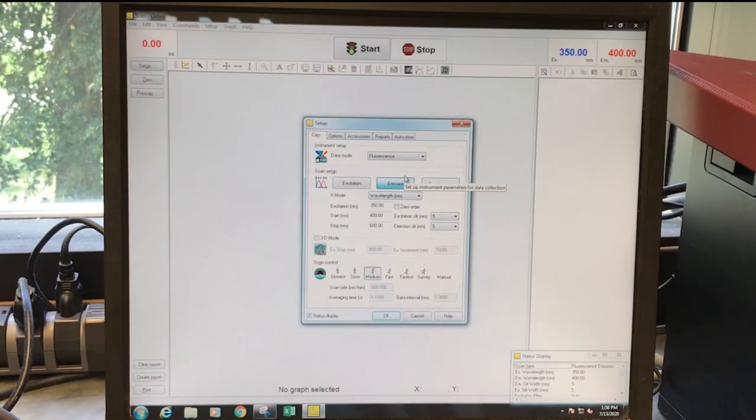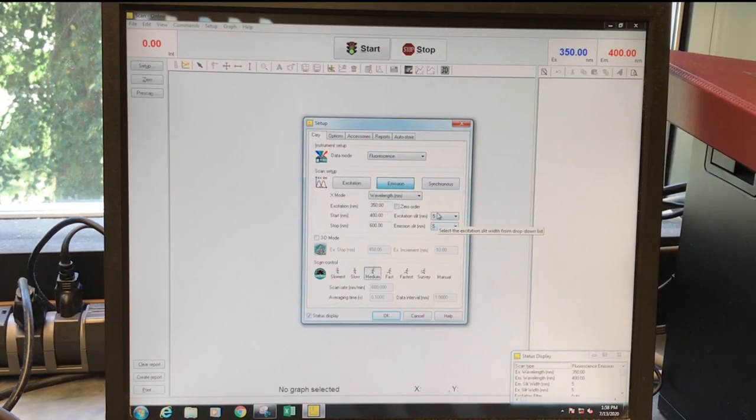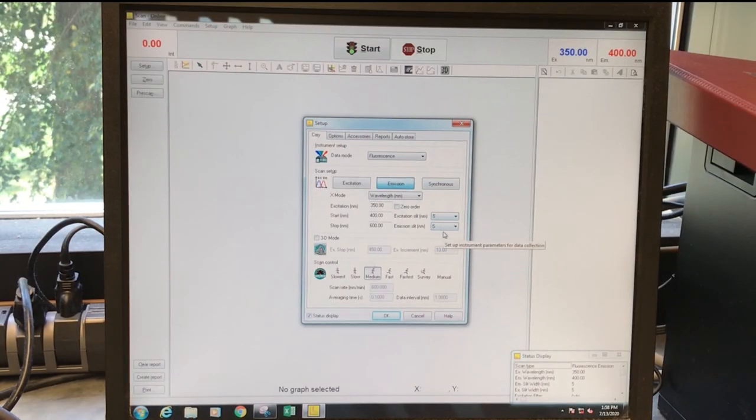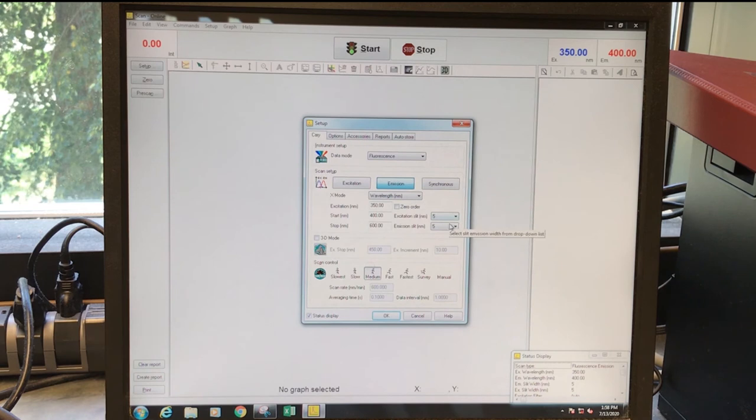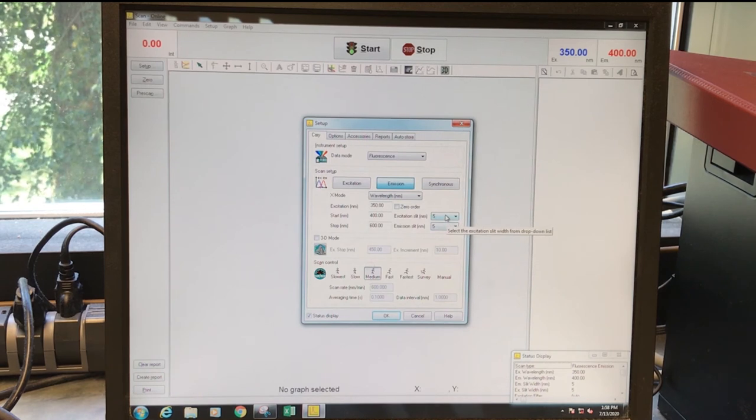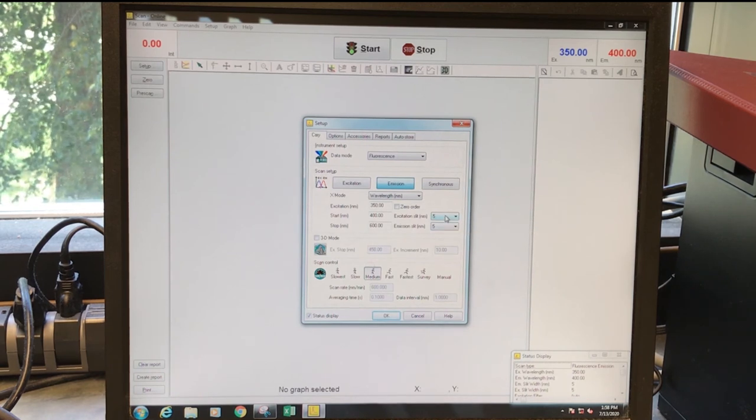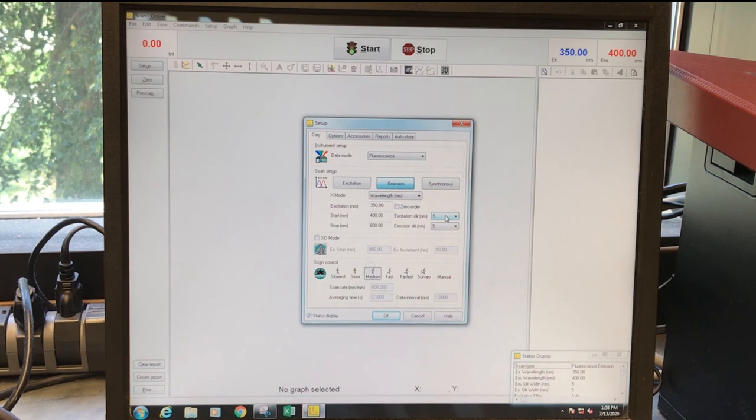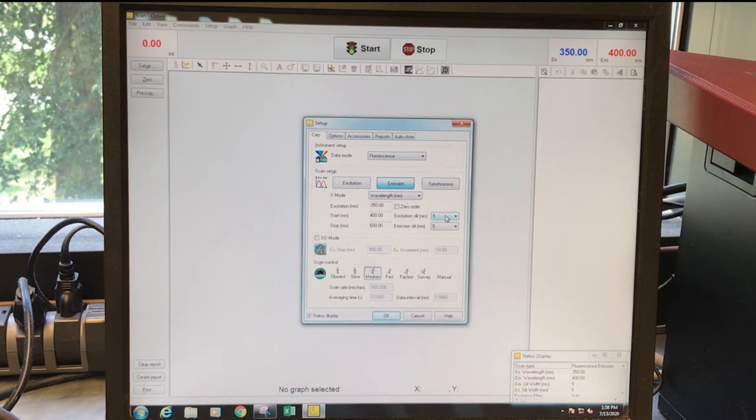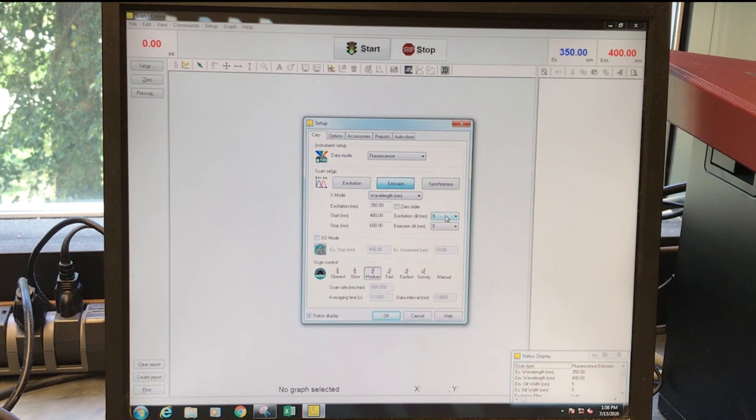And so another thing you'll want to look at are the slit widths. These are something that you may need to change depending on your sample.